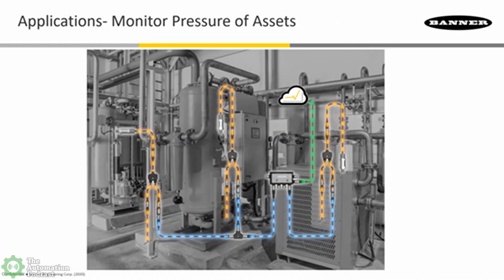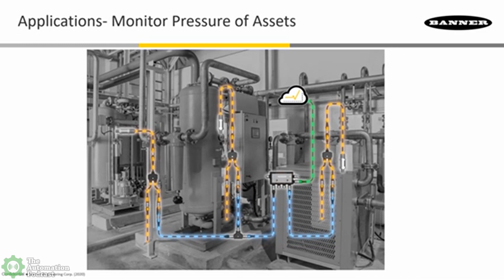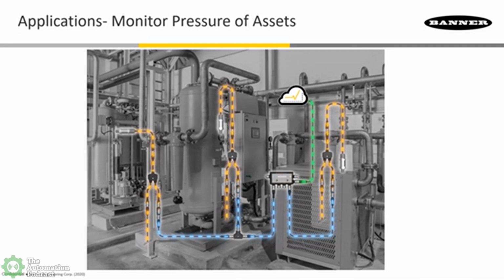And lastly, pressure monitoring—being able to take a 4 to 20 milliamp output of a pressure sensor to monitor pressure of some of these critical assets. You could convert that 4 to 20 signal over to a unified serial protocol, and have dozens of these pressure sensors or a mixture of different sensors going back to the DXMR90 industrial controller.